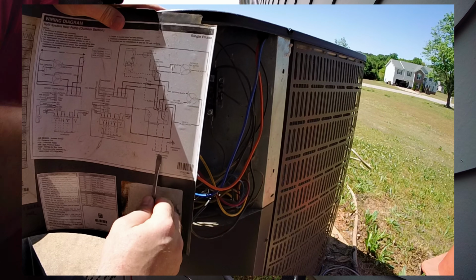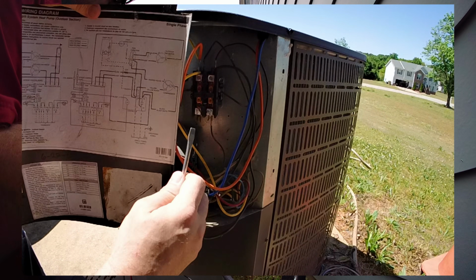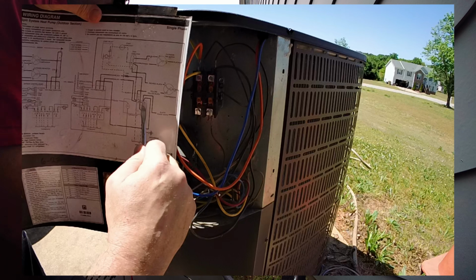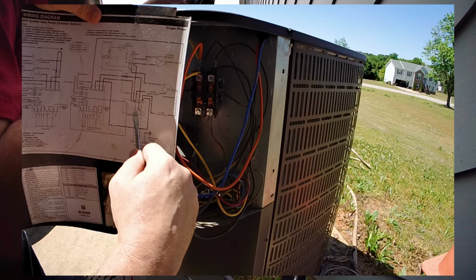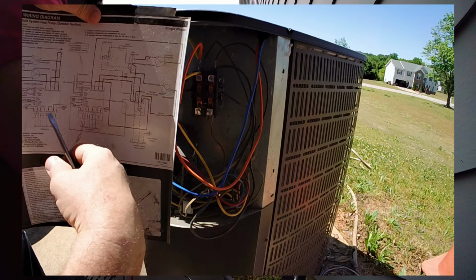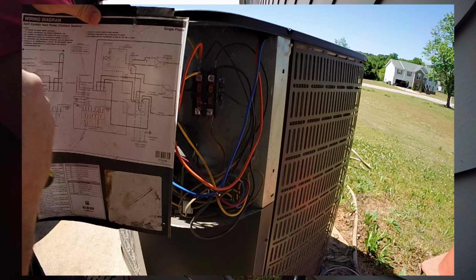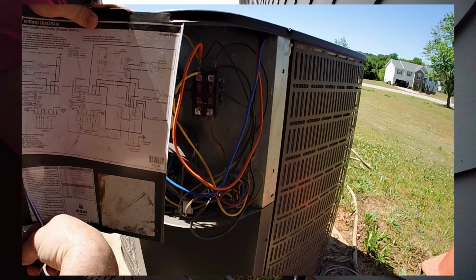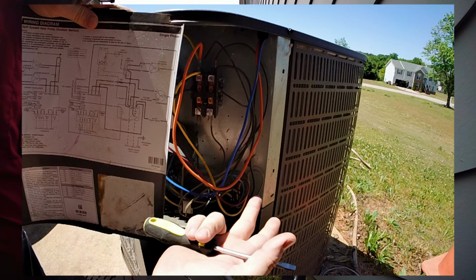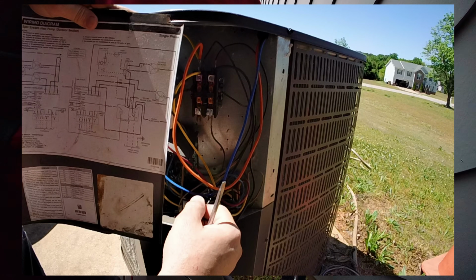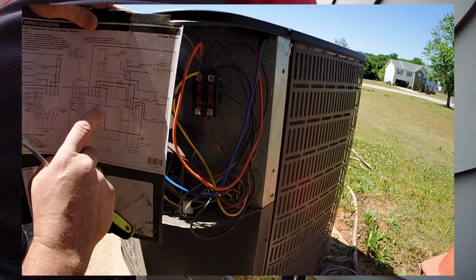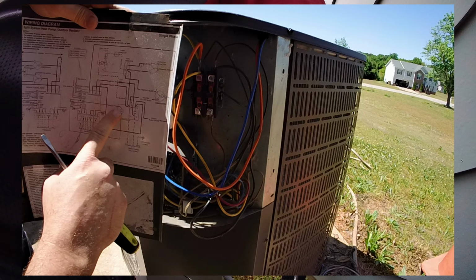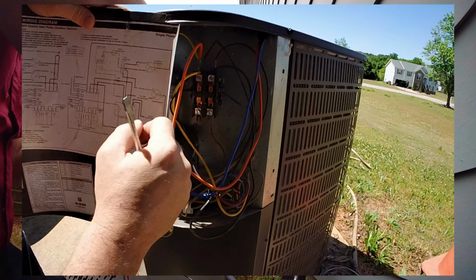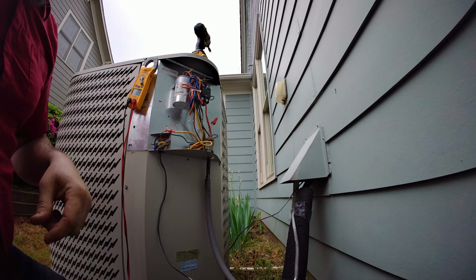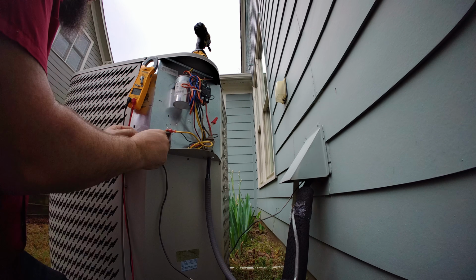You know, obviously you can use your nice little wiring diagram you see here. Line 1, line 2 goes and completes our circuits through our various devices, comes through on the other side. This one is depicting a single pole contactor, so that's been changed either by me or somebody else in the past. Again, for our purposes on these guys, doesn't really matter that much. There's our contactor coil where our low voltage is connecting here, so easy enough. Resecure our low voltage here.